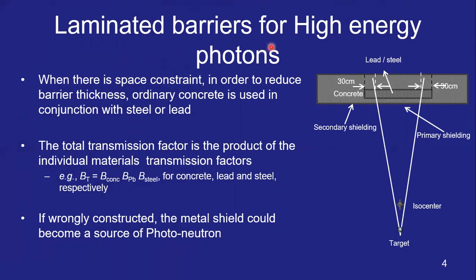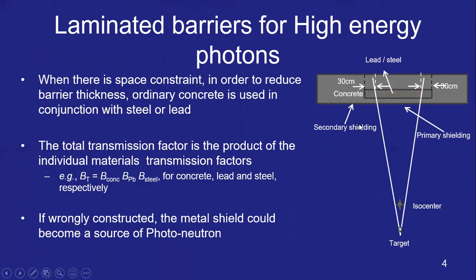We will look at laminated barriers for high energy photons. When space becomes a constraint, in order to reduce the actual barrier thickness, one can use metals like steel or lead within the regular concrete. In such cases, the total transmission factor is the product of the individual material transmission factors. So the total transmission B_T equals B_concrete multiplied by B_lead multiplied by B_steel if steel is also present.